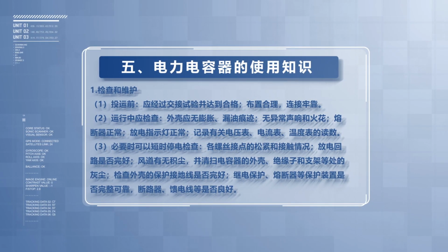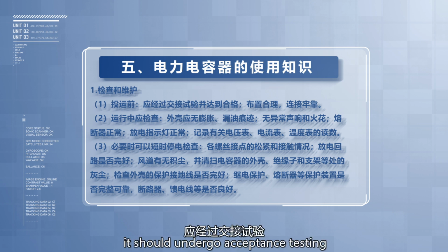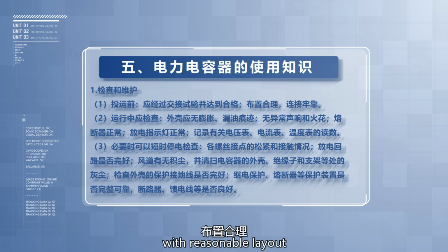Inspection and maintenance. Before commissioning, it should undergo acceptance testing and meet the qualifications, with reasonable layout and firm connections. During operation, check that the case should not be swollen, no oil leakage traces, no abnormal sounds or sparks. Fuses, discharge indicator lights should be normal. Record the readings of related voltmeters, ammeters, and thermometers. If necessary, you can briefly power off and check.